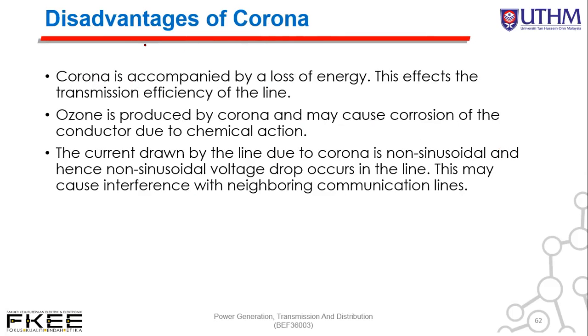However, there is the disadvantage of corona, that is, corona is accompanied by a loss of energy. This affects the transmission efficiency of the line. Okay, energy loss, so efficiency reduced. Ozone is produced by corona and may cause corrosion of the conductor due to chemical action. Okay, corrosion. The current drawn by the line due to corona is non-sinusoidal. And hence non-sinusoidal voltage drop occurs in the line. So this may cause interference with neighboring communication line.